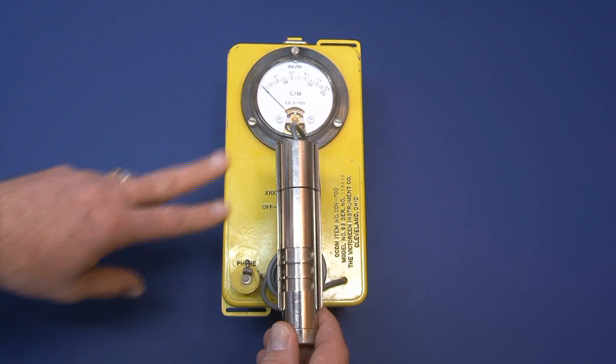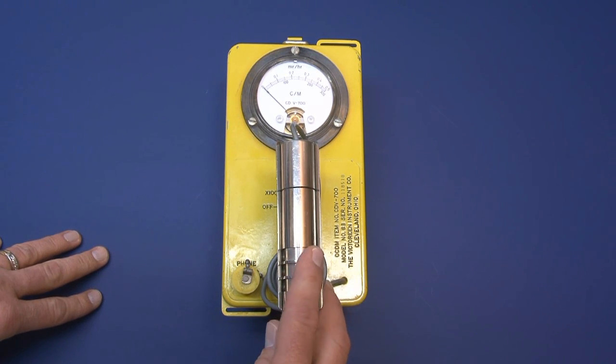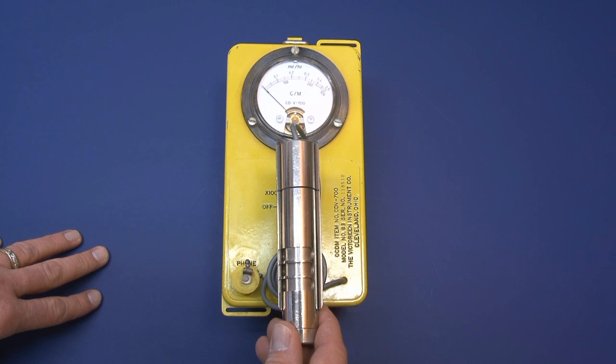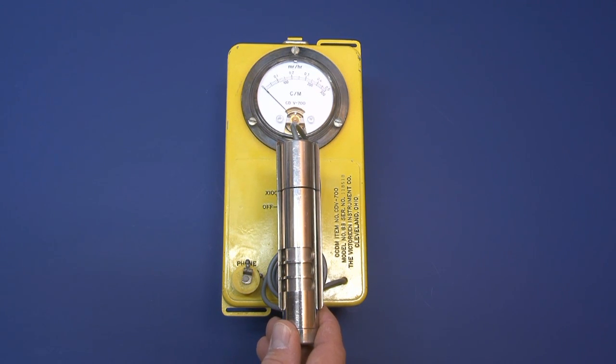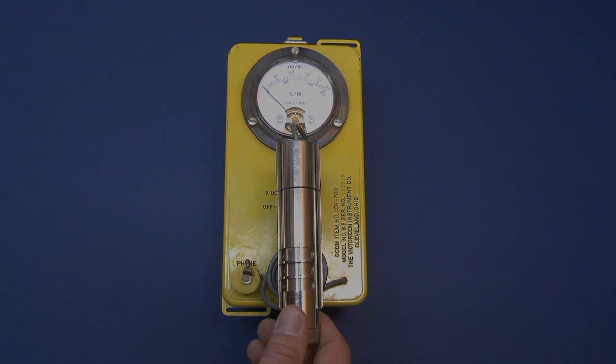It's important that you don't store the instrument for a long period of time, usually greater than 30 days, with the batteries in place. If you store it with the batteries in place, you can have battery seal failure, and that will ruin the inside of your instrument. So make sure you take those batteries out if you're going to store the instrument.